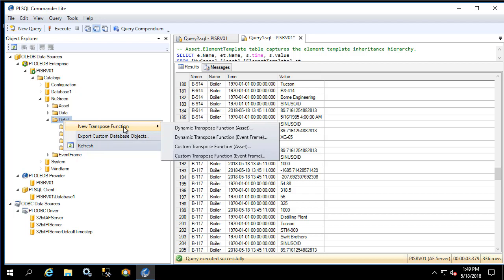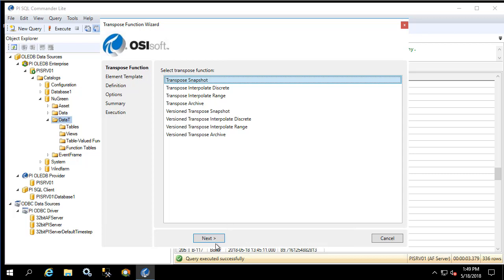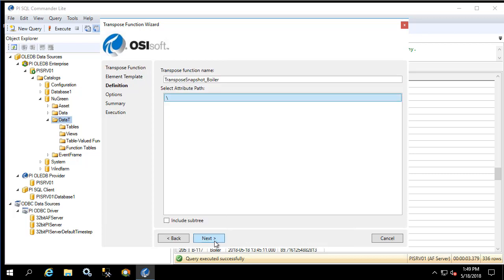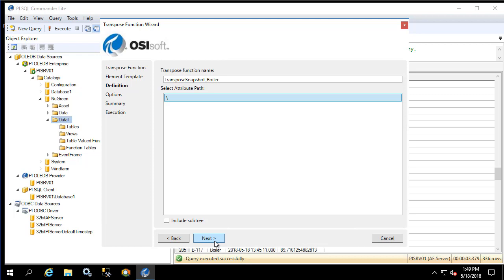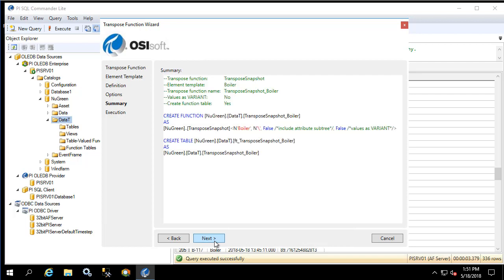We'll start by doing dynamic. We'll create a snapshot transpose function and select the boiler template. All of our attributes are root level attributes, so in this menu we'll select just the root path for the attribute. Selecting values as variants will cause the transpose function to return variant as the data type for all the attributes. Create function table will create the function table as well as the table value function. Some SQL applications are not compatible with functions, therefore the function table will be necessary in those applications. We recommend creating the function table in addition to the table value function just in case. Let's click Next and execute the query.